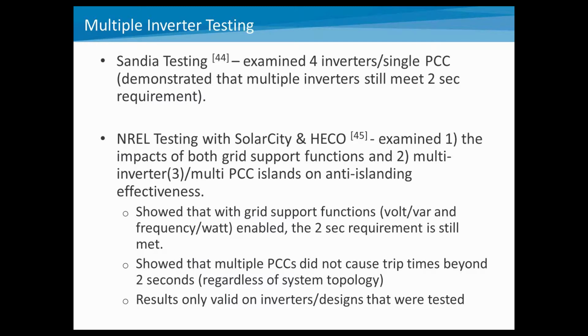Some recent testing that was just released here in July of this year, so last month, was testing that NREL completed with SolarCity and HECO to examine 2 additional things. 1, what's the impact of these new grid support functions, so allowing things like low voltage ride-through, volt var support on the anti-islanding conditions, and 2, what about multiple inverters and multiple PCCs, and what's their effect on anti-islanding? So the outputs of this, I'm not going to spend a huge amount of time. This is probably an additional presentation that we could give in the future.